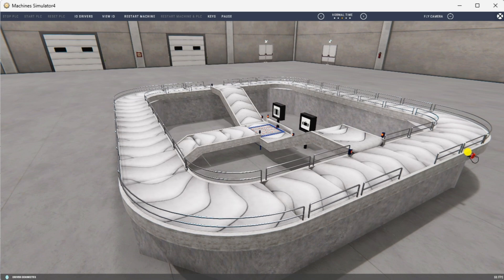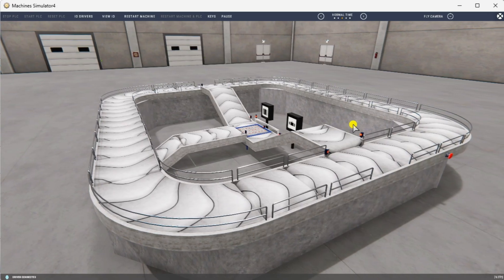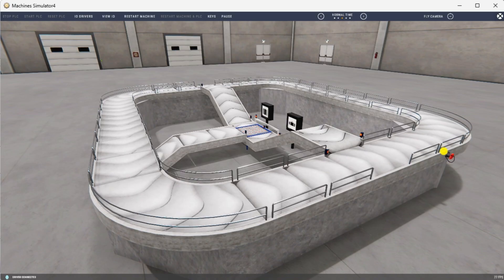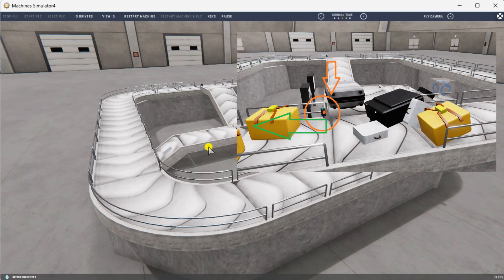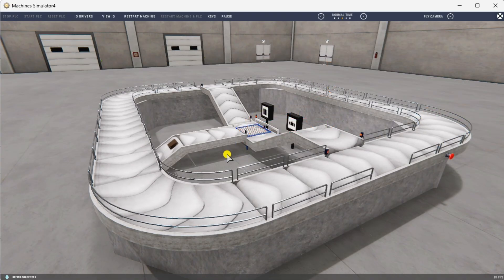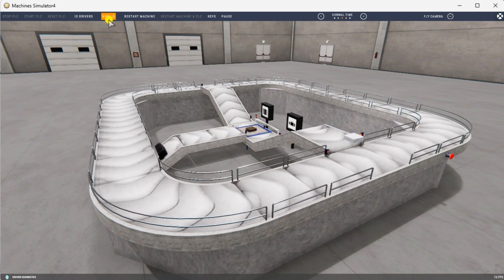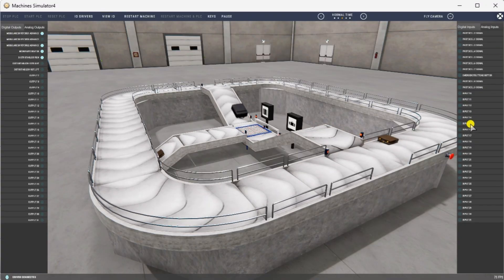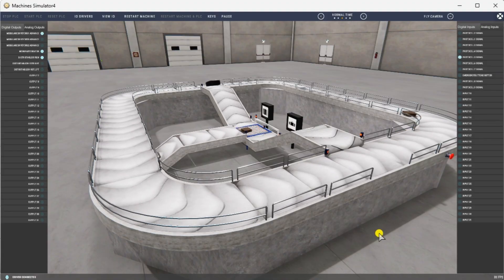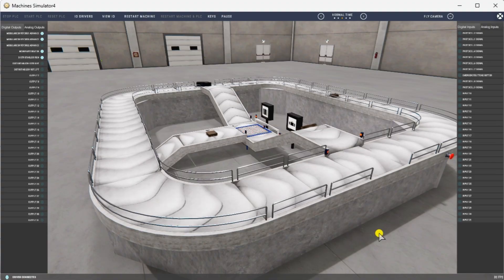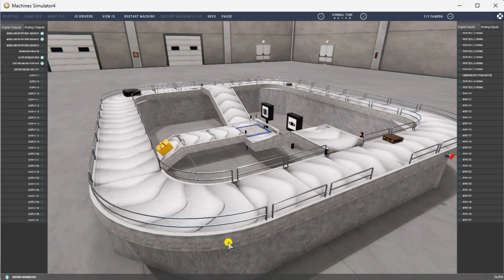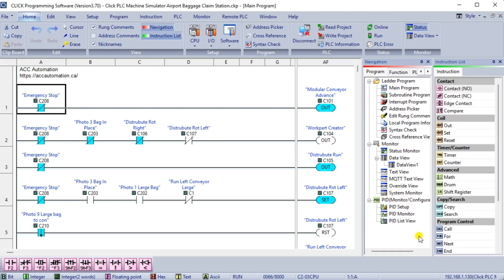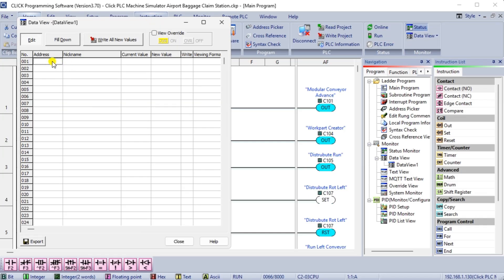On the bottom left side of the window, the driver communicates with the CLICK Plus PLC. Ensure that the CLICK PLC is in run mode. We can see the operation of our baggage belt machine. Test the machine to see if errors occur. We know from our sequence of operation that the sensor entry to the main conveyor for the large bag will falsely trigger on some of the bags — mechanically this must be moved. Our program used the one shot to compensate for the sensor location. Select View I/O to know the input and output status of the machine simulator. The digital inputs and outputs of the MS will correspond to the PLC controller. Using the data view window of the CLICK programming software, we can also watch the input and output operations. Using the machine simulator MS to test the program will ensure that our program works. Troubleshooting is quickly done without damage to any physical hardware.